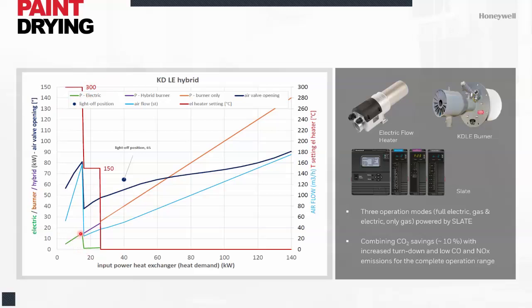After this, we can switch into a hybrid mode where the burner is enabled and running. We give it a bit of preheat to optimize the combustion and lower CO emissions. Then, once we know we can guarantee the CO emission limits, we go into a full combustion mode up to maximum capacity.